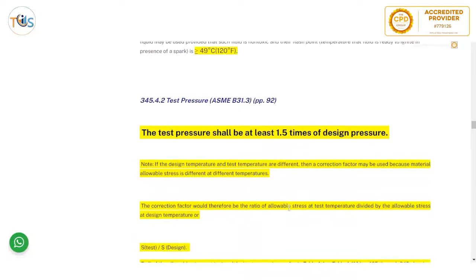Now, if the design temperature and test temperature are different, then a correction factor may be used, because material allowable stress is different at different temperatures. Remember, we went to table A1 and we saw that the material allowable stress is reducing as the temperature is increasing. So if the design temperature, the working temperature, is some high temperature, and the test is done at ambient temperature, that means less than, say, 100 degrees Fahrenheit, then you have to use a ratio. That means the allowable stress at test temperature divided by allowable stress at design temperature. That would be the factor you have to add. So eventually the test pressure goes up. It's not only 1.5 times, it will be more than that actually, the pressure itself, absolute pressure.